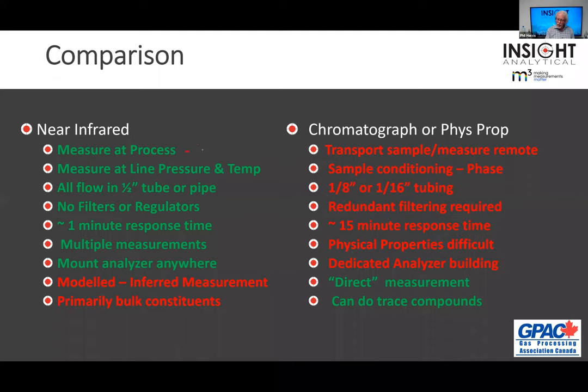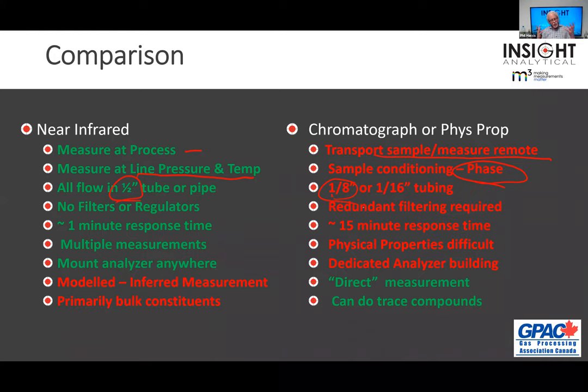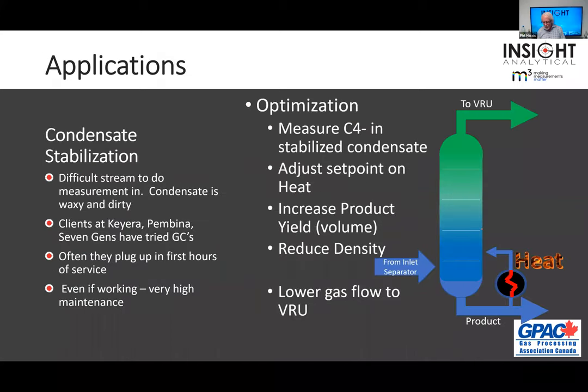Comparing infrared spectroscopy to a GC: with infrared, we measure right at the process; with a GC, we transport the sample to a remote location. That transportation creates pressure drops, and with liquids we get bubbles and phase change. With infrared, we keep everything at the same pressure and temperature as the process and assume single phase. Flow is through half-inch pipe versus eighth-inch tubing, with no filters or regulators — those are things that plug and require maintenance. We just flow through the cell and back out. We go through all these features, but really the key is simpler, lower-maintenance measurement right at the process.